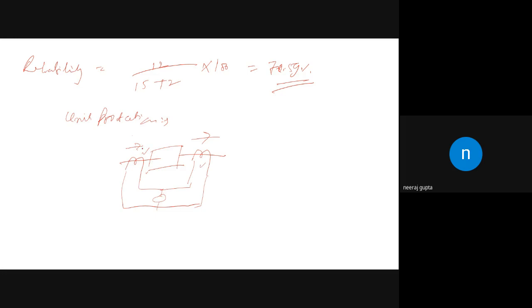We can see whether there is a difference in the current. Let us suppose that a fault occurs in the system. Whatever current is flowing here is different from the current flowing in the second CT, and as a result the difference is there, the trip signal is given to the relay and the relay will operate. So this is the differential protection.